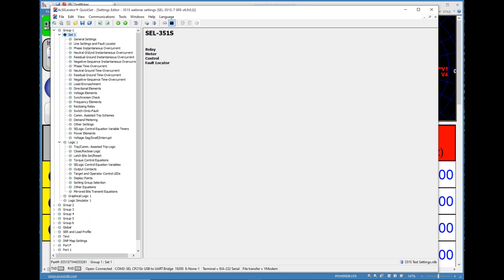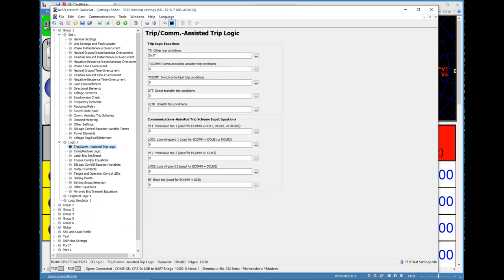For our testing purposes here, I've set up a few elements: the phase instantaneous overcurrent, neutral ground overcurrent, residual ground instantaneous overcurrent, phase time overcurrent, neutral residual ground element, voltage elements, and frequency elements. I also need to look at my trip logic. The trip logic is more of an example to show the difference between testing element-based versus logic-based testing.